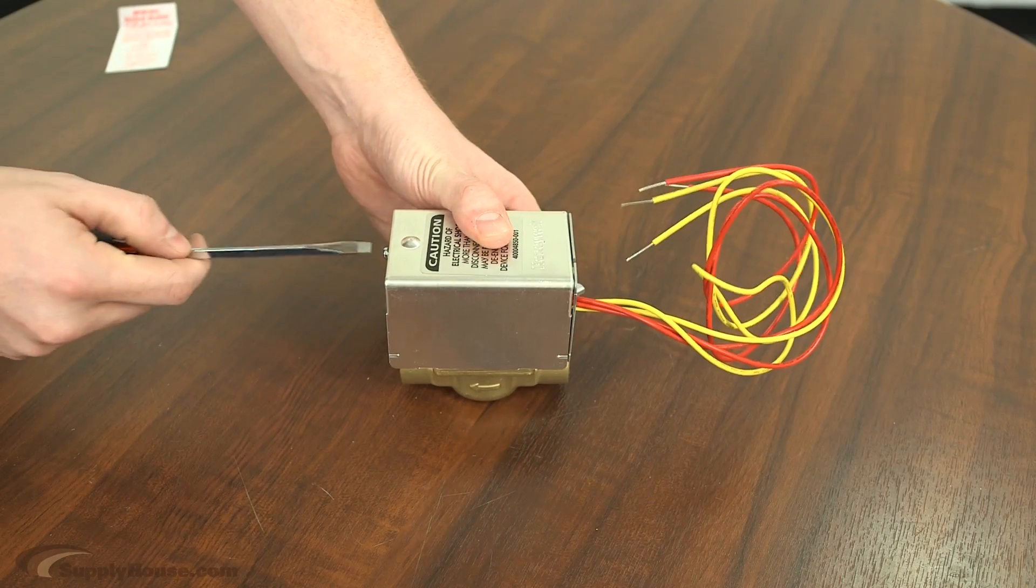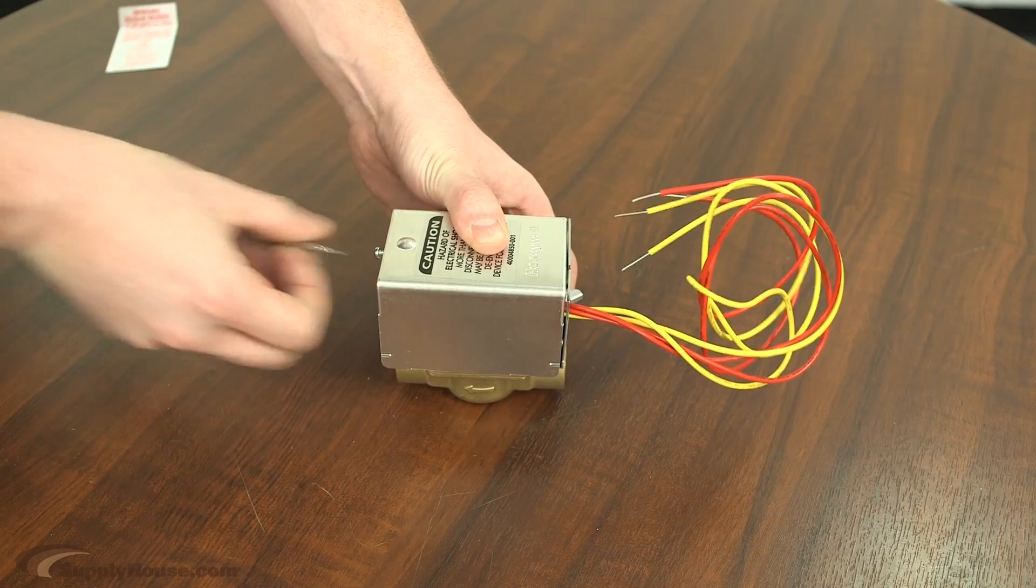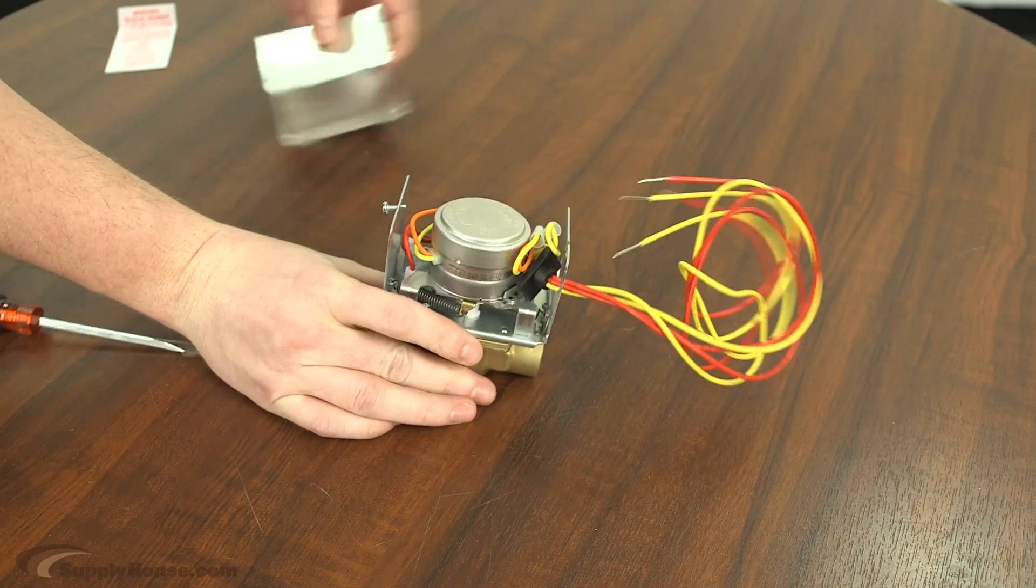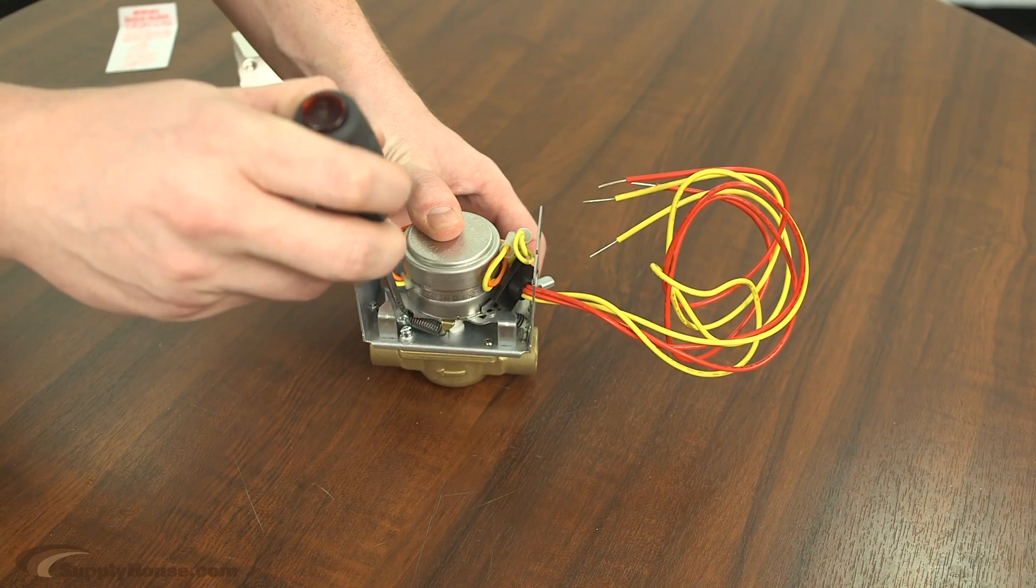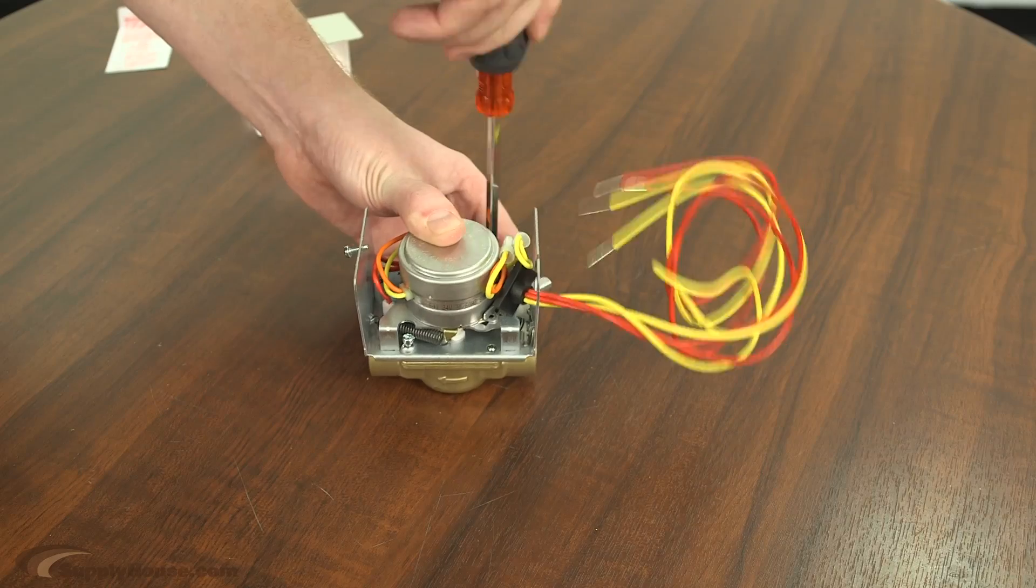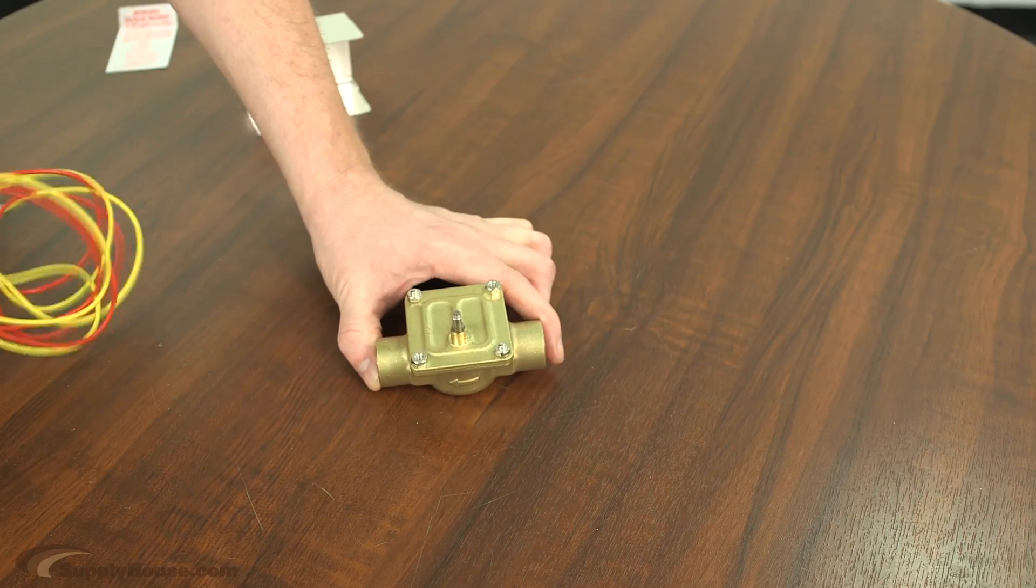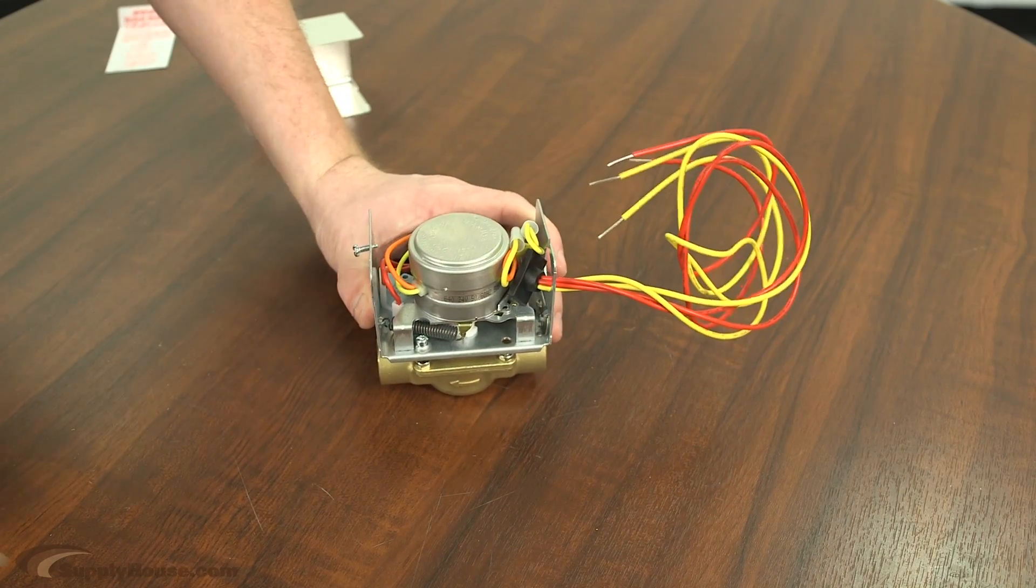For the Honeywell zone valves, you need to remove the cover. Then you have to unscrew the actuator from the valve body. There's two screws diagonally from each other. Once the screws are done, you just pop that bad boy off, put on the new one, screw it back in, and rewire it.